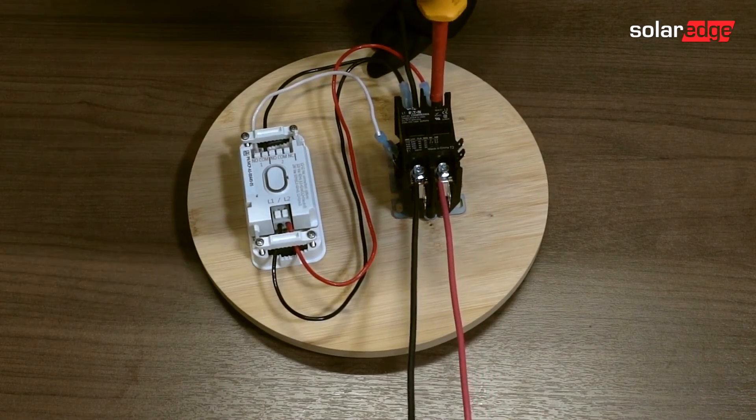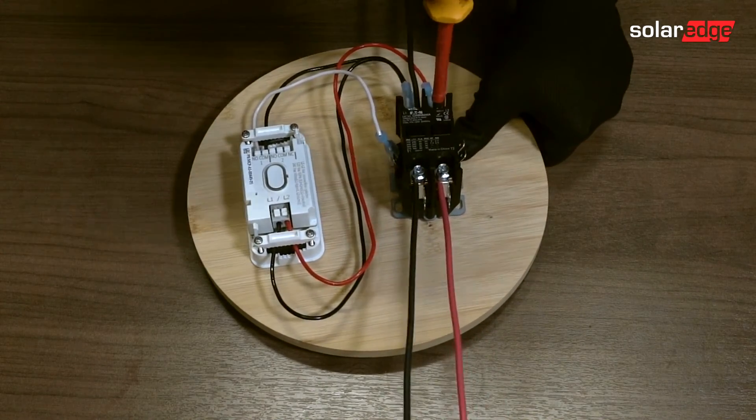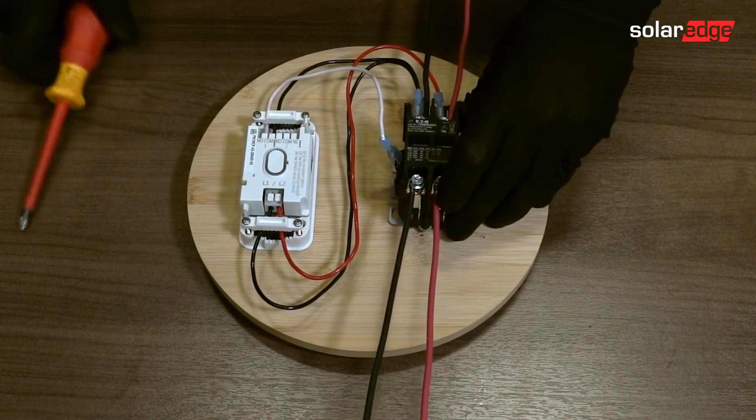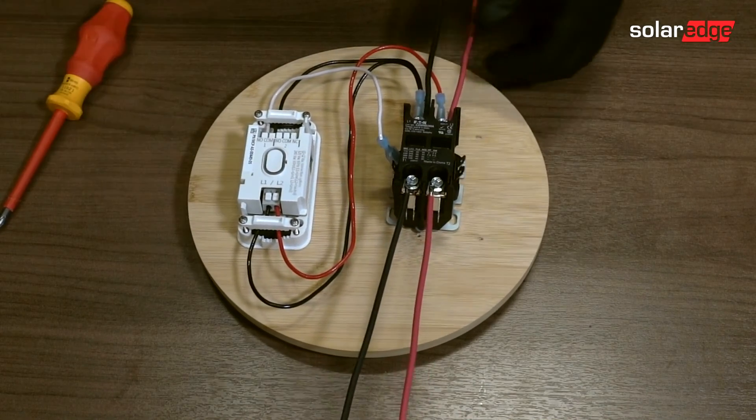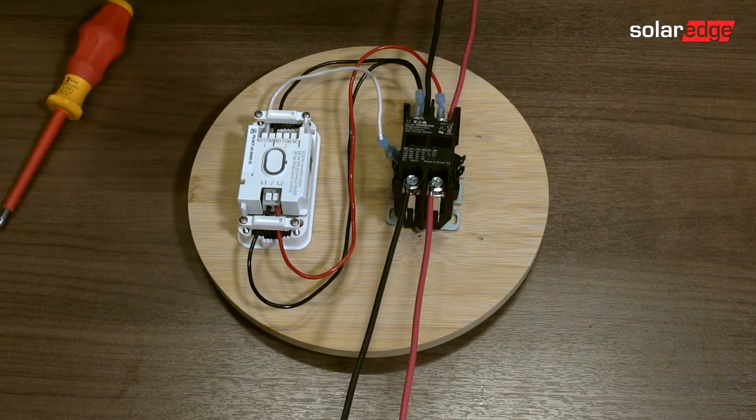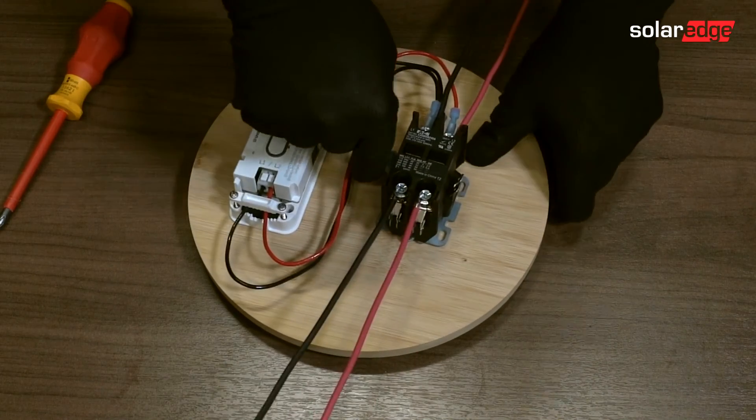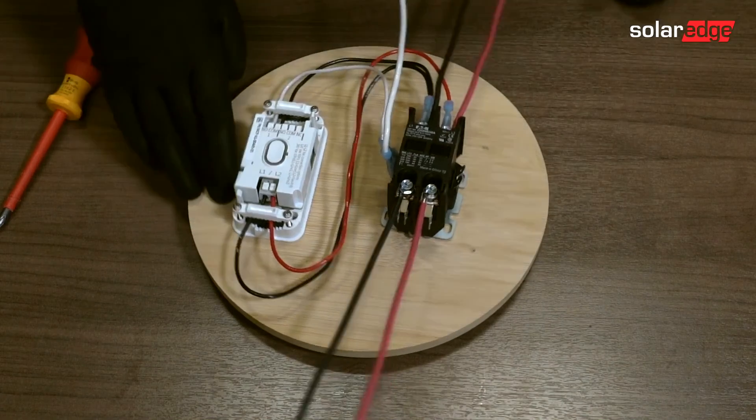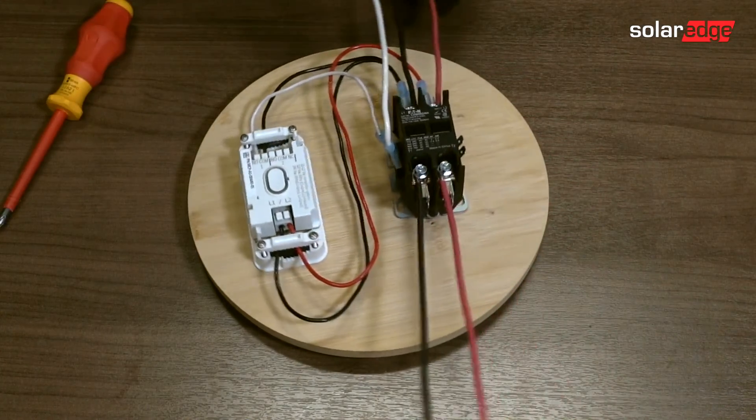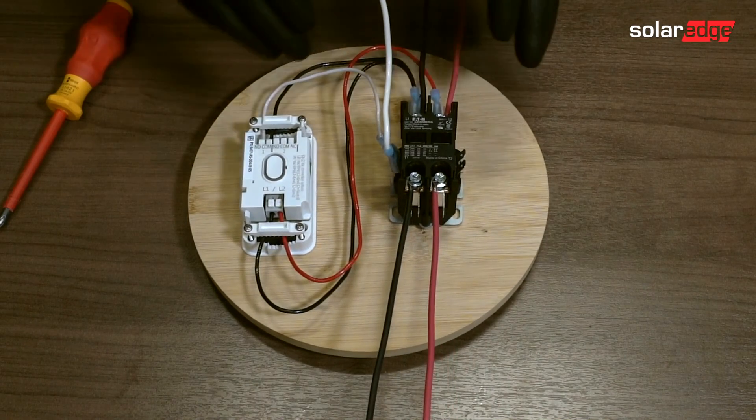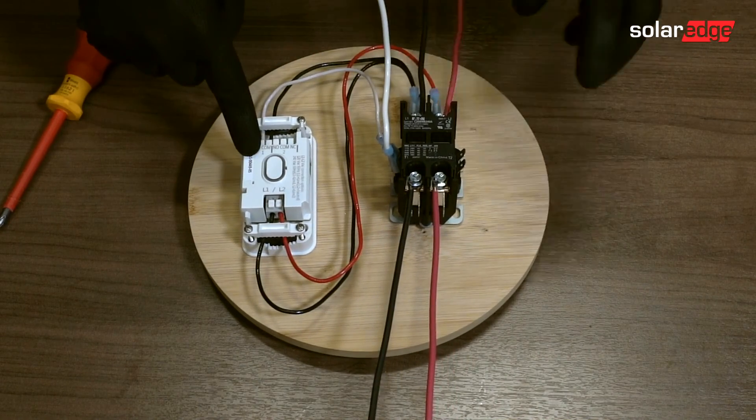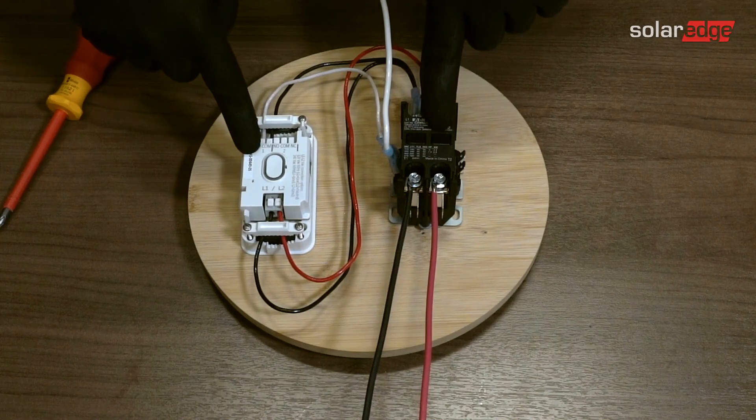Alright, I gave myself a nice little wire loop so I could really torque down on those conductors. And then the last one is going to be from the neutral bar to the coil. So I have a 120 volts coil. And that is how you wire a SolarEdge load controller to a contactor with a 120 volt coil.